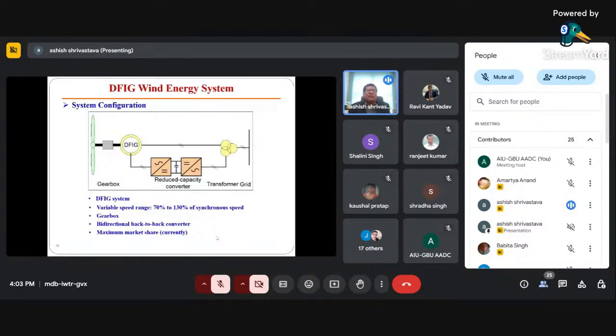Now this is the basic system diagram in which you can see one power flow is happening from the windmill to the gearbox to the doubly fed induction generator, and from the stator the power goes to the 3-phase transformer and to the grid. But from the transformer you can also inject power to the rotor. That's why it is called doubly fed. So from AC to DC, we maintain the DC link voltage at the capacitor, and then DC to AC of reduced frequency. That means at s times the fundamental frequency, it has to be converted. So it is at a reduced voltage level.